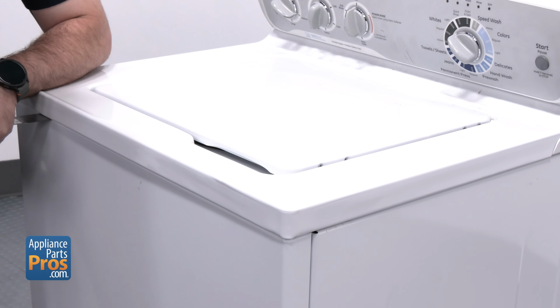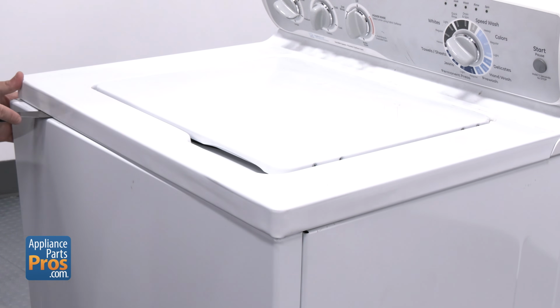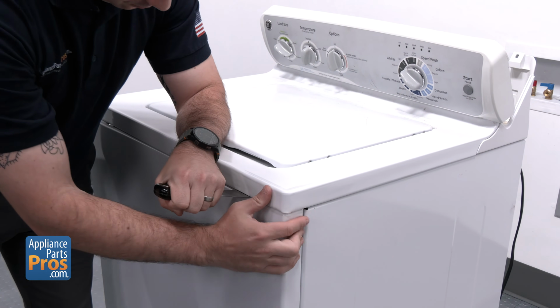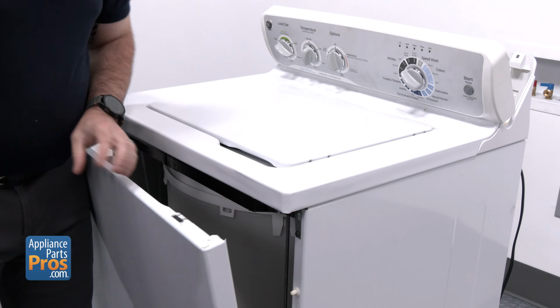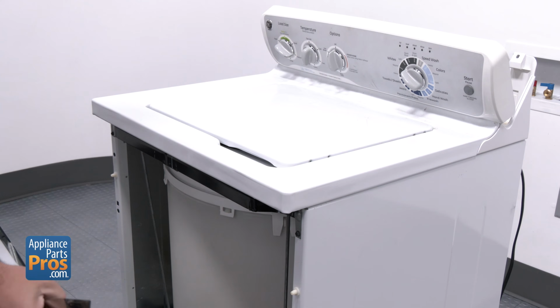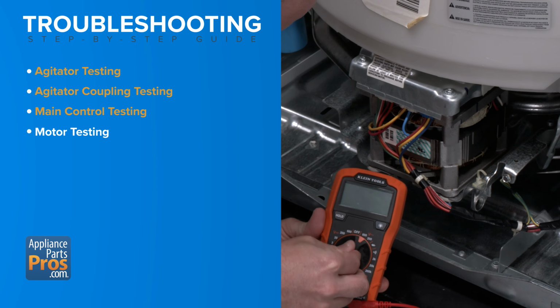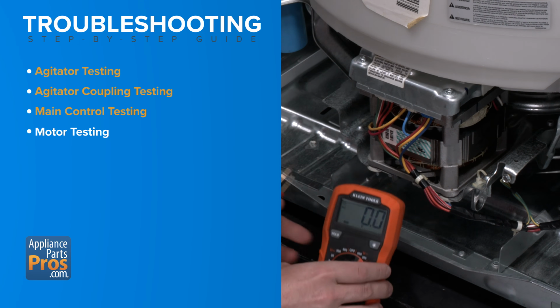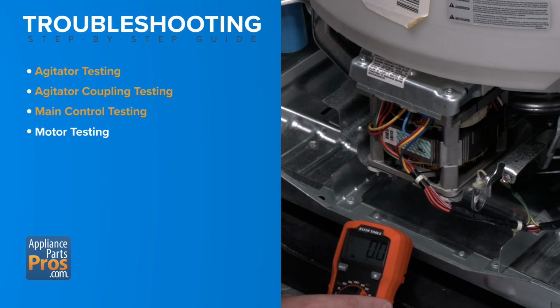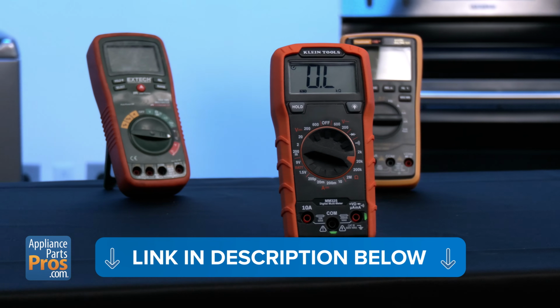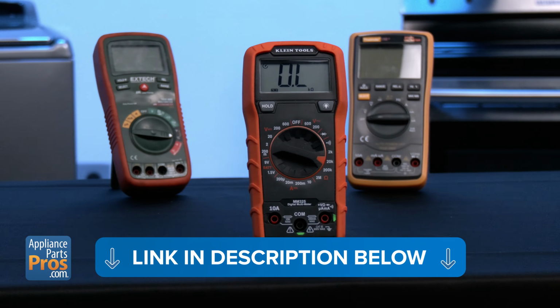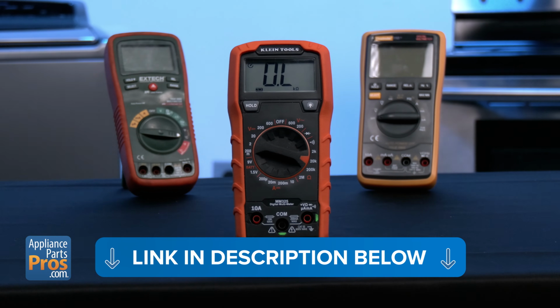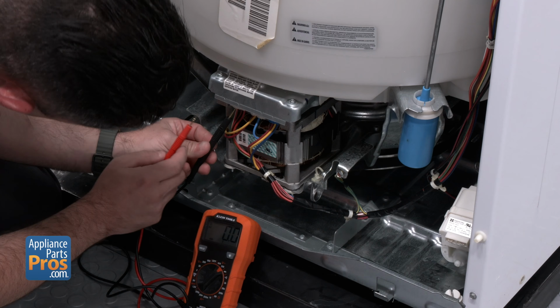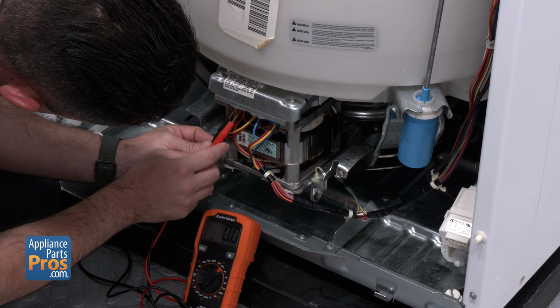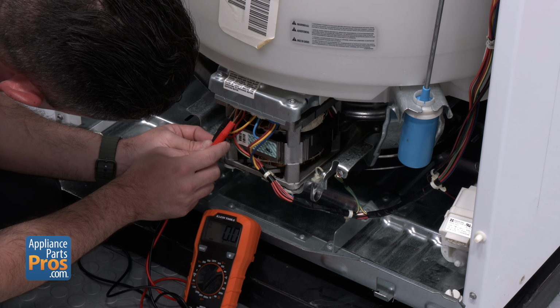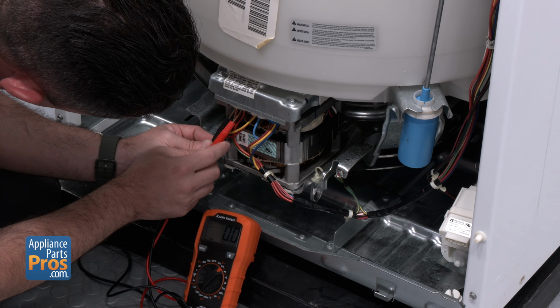Grab your putty knife and insert it about 3 to 4 inches from each corner at the top of the front panel to release the locking tabs. Rotate the front panel forward, lift it up, and set it aside. Locate the motor harness. Set your multimeter to volts AC, indicated by a V with a squiggly line. If you're unsure how to use a multimeter, we put together a helpful tutorial. Check out the link in the description for step-by-step instructions. Test from the red wire with a black stripe to the white wire with a red stripe. You should see 120 volts AC.